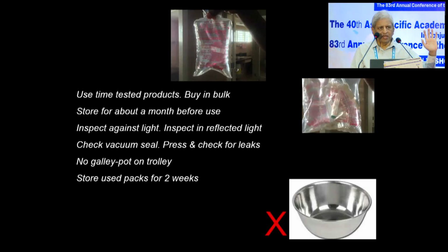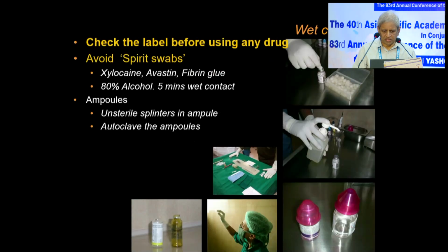Inspect against light like this, as well as in reflected light, and then you will pick up the particles. Don't shake it up, gently move it so that you see the particles moving around in case it's contaminated. The vacuum seal has to be seen. If the vacuum seal is released, it's unsterile. And never use a galley pot on the trolley. Store used packs. This is a used one. We don't discard it. We put it in a plastic cover, label it and put it somewhere. And after 2 weeks, we discard it. So in case a patient has a problem, we have something available with us for investigations.